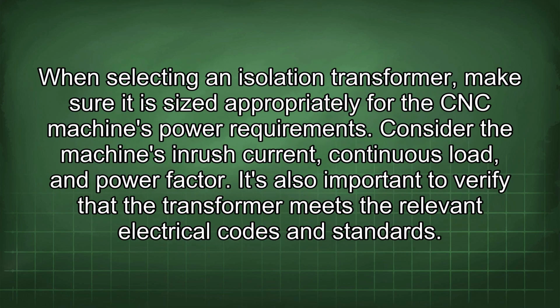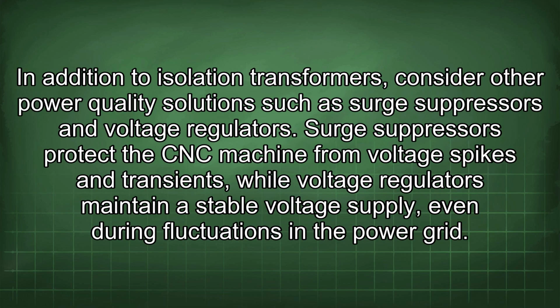When selecting an isolation transformer, make sure it is sized appropriately for the CNC machine's power requirements. Consider the machine's inrush current, continuous load, and power factor. It's also important to verify that the transformer meets the relevant electrical codes and standards. In addition to isolation transformers, consider other power quality solutions such as surge suppressors and voltage regulators. Surge suppressors protect the CNC machine from voltage spikes and transients, while voltage regulators maintain a stable voltage supply, even during fluctuations in the power grid.